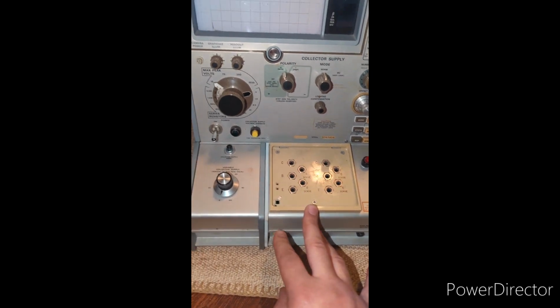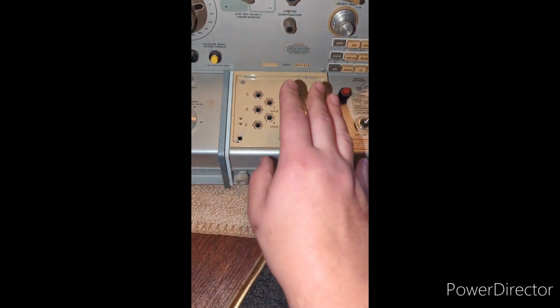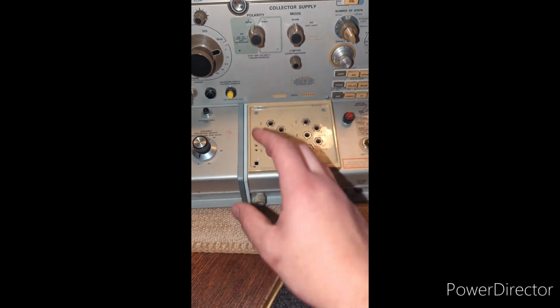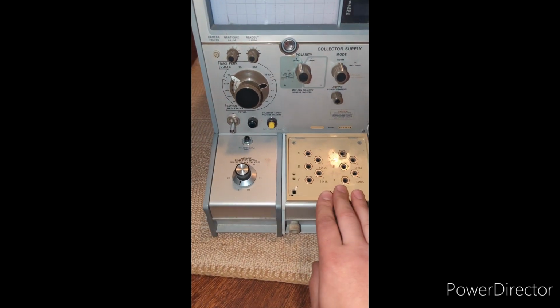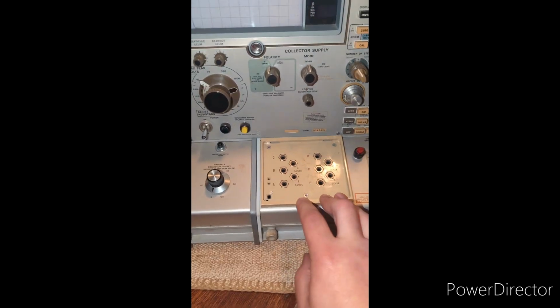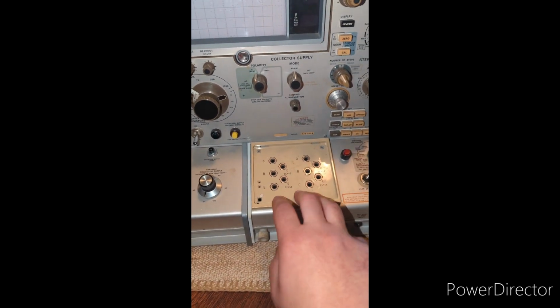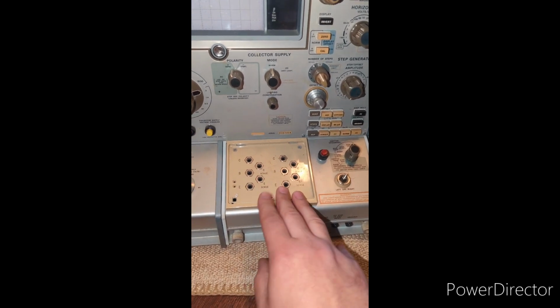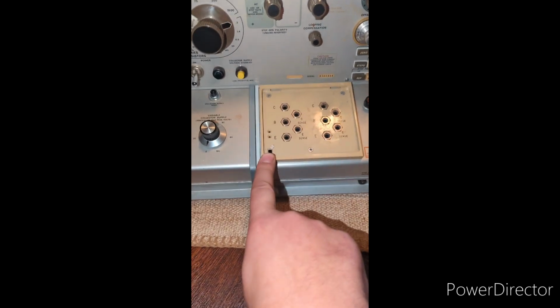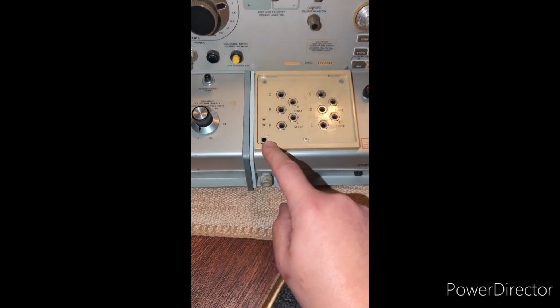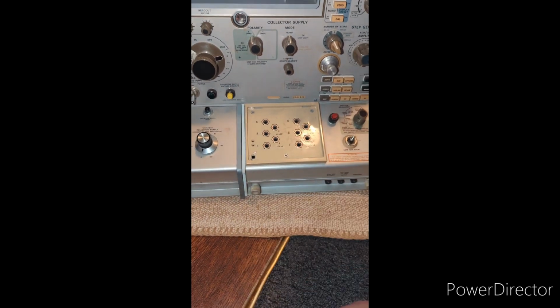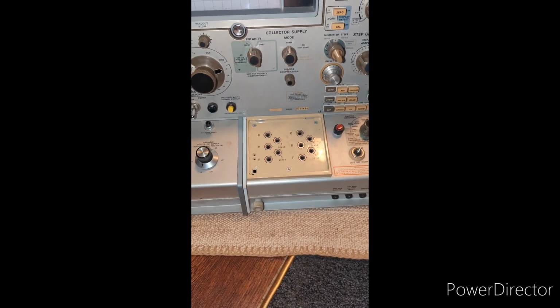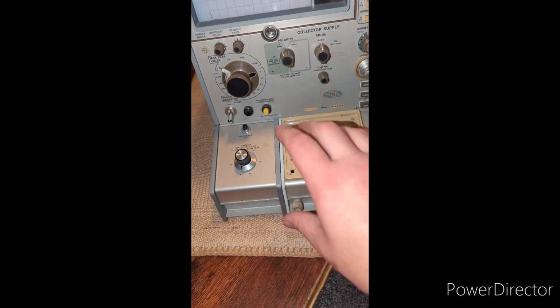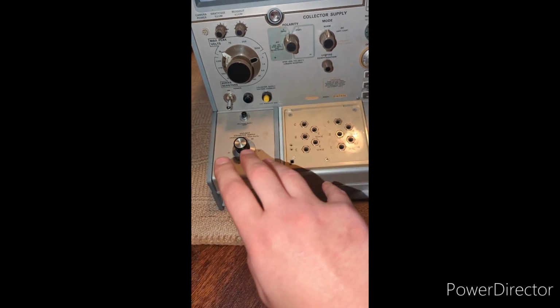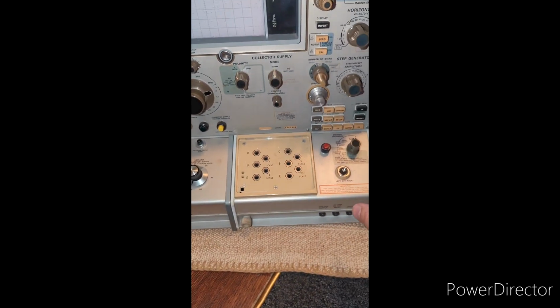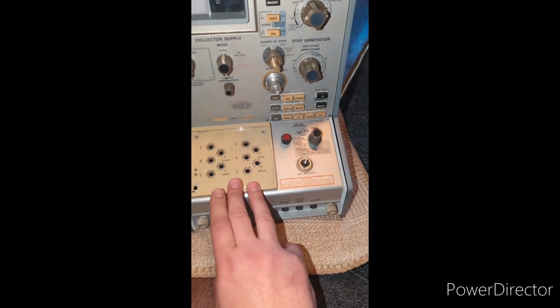And another thing, speaking of testing at higher voltages, is there is a plastic cover that goes over top of this when you have it at voltages greater than 15 volts. And in fact, it will not work at higher voltages without that. And there's a little button that is actually stuck in the depressed position there that I would assume would get triggered when you put the cover over it and disable the high voltage interlock. So that is also something I noticed.